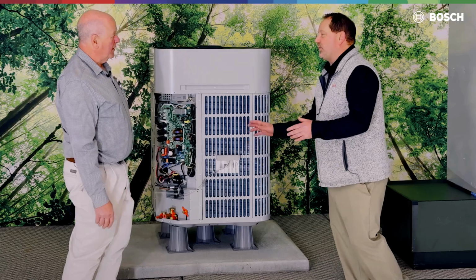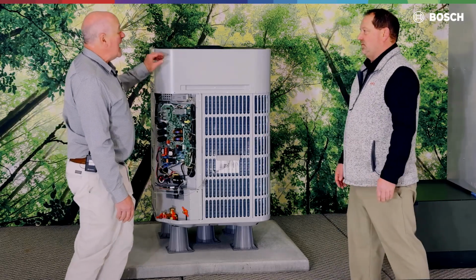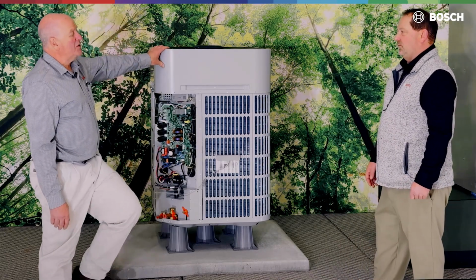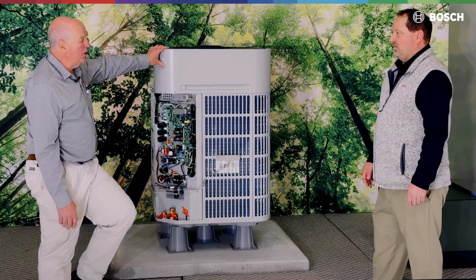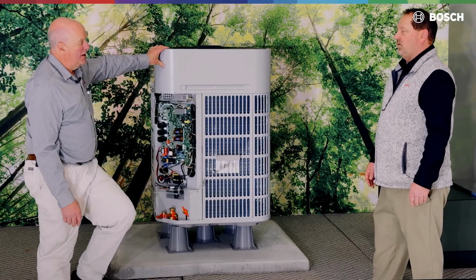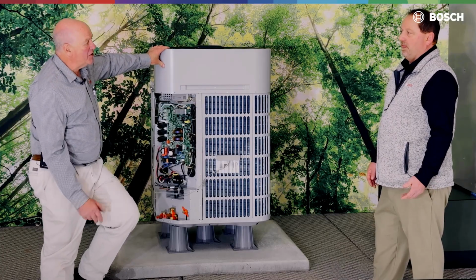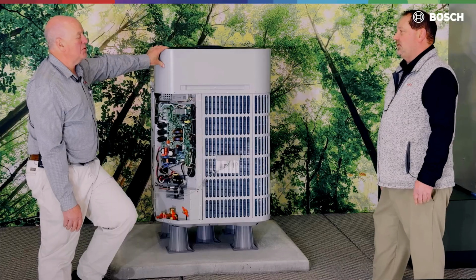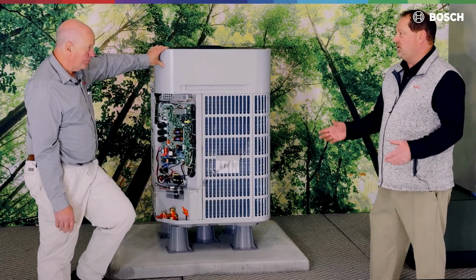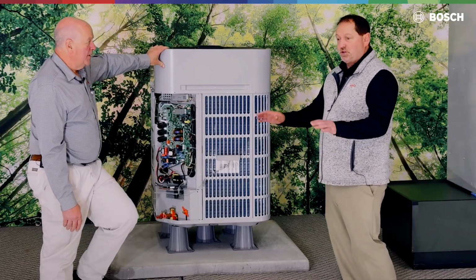Is it going to hurt if I pressurize this above 250 pounds? It can. The issue is the service valves may let that bleed through into the compressor section. We've heard rumor of that. I've not seen it firsthand, but I've heard some rumor of that application. It is possible. So stick to what the IOM says. The IOM says 250 PSI should be plenty good.